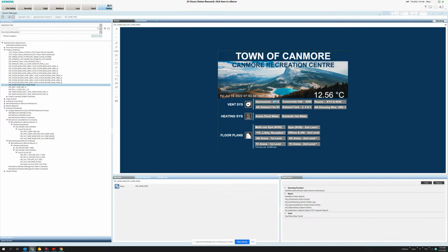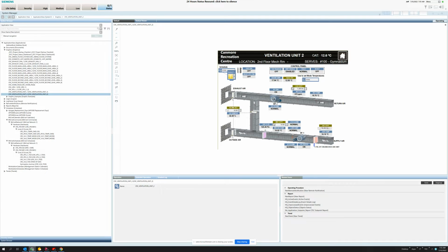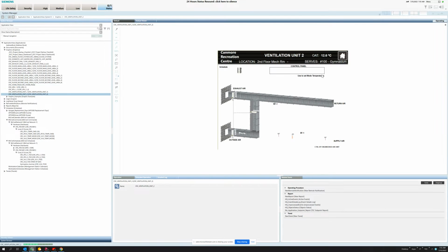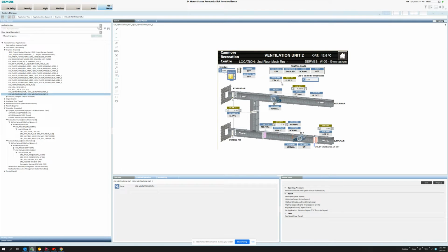Okay, I wanted to show you what I'm seeing. So in gymnastics, room 100 VU2, it's going into fault whenever there's a change that's requested, but it is reflecting the requested temperature. So whichever temperature it's asking for in the table, it does seem to be updating here.